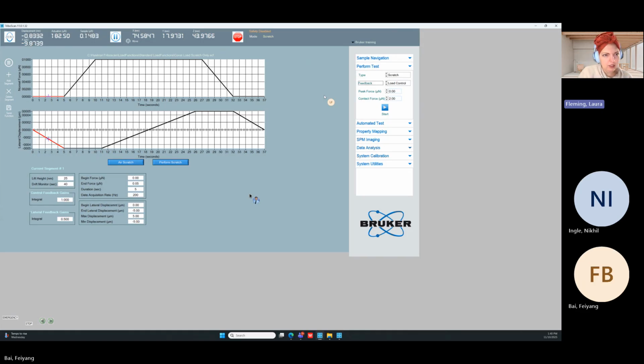Let's see, what else have we got? The system has a maximum force in X of 2 millinewtons, but there's nothing to stop it. So you have to be smart and think about what you're testing. People often try to go really big on scratches, and that typically results in very blunt probes and poor data, because if you go too far, you can actually get stuck in the material, and then instead of scratching, it will just lean and then skip along the sample surface. So scratch is, I mean, all nano indentation is very physical. But with scratch specifically, you have to be very careful and pick parameters very carefully. So let's go ahead and walk through this load function.